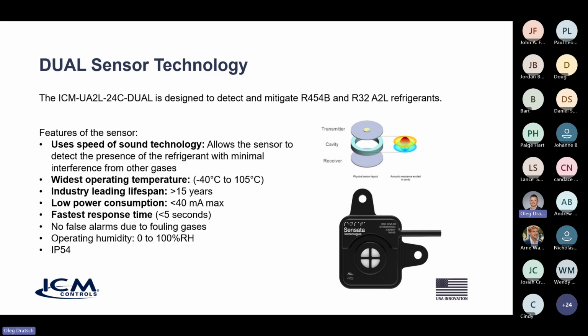So the sensor itself uses speed of sound technology. This is the sensor that is the best sensor in the marketplace. A lot of the testing that UL does, this is the benchmark. So this is really the Cadillac of all sensors, if you will. It has the widest operating temperature, from minus 40 degrees C all the way up to 105 degrees C. That's, again, tops in the market. I don't believe anybody goes above 85 or 95 degrees C today. As I mentioned earlier, greater than 15-year lifespan. Lab testing is indicating anywhere from 18 to 28 years of lifespan.